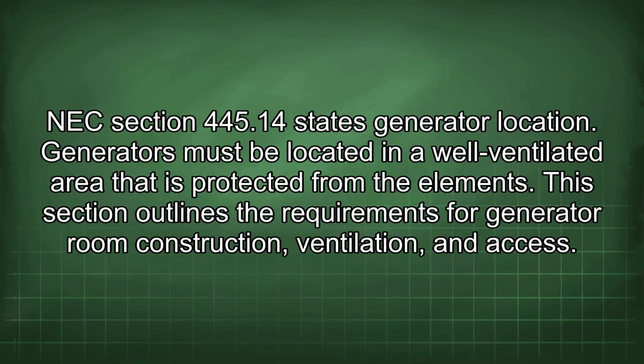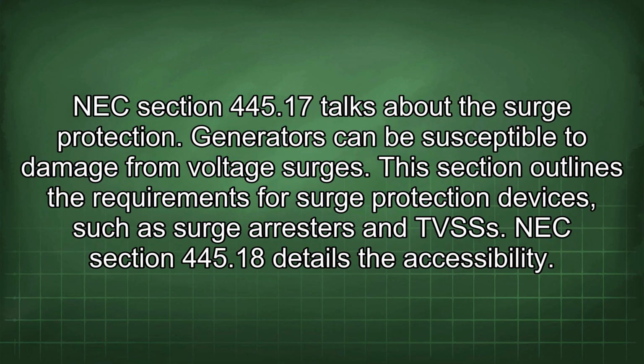NEC Section 445.14 states generator location. Generators must be located in a well-ventilated area that is protected from the elements. This section outlines the requirements for generator room construction, ventilation, and access. NEC Section 445.17 talks about surge protection. Generators can be susceptible to damage from voltage surges. This section outlines the requirements for surge protection devices, such as surge arresters and TVSS.